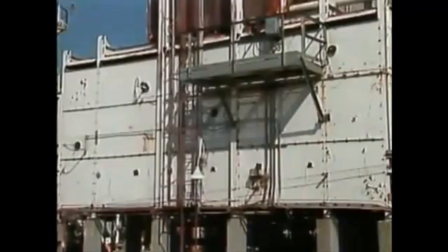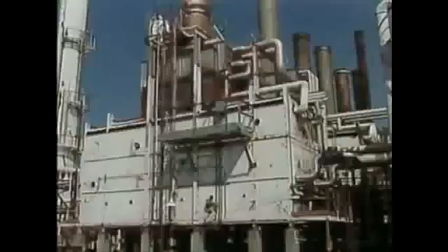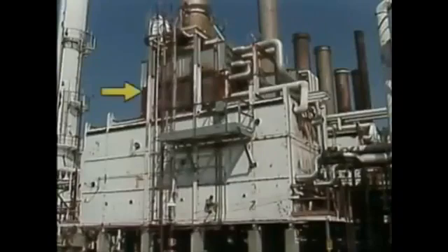When fuel is burned, it produces flue gases. A process variable that's closely watched is the flue gas temperature. Flue gas and other furnace temperatures are usually measured with thermocouples. Flue gas temperature is often measured in the convection section and in the stack.